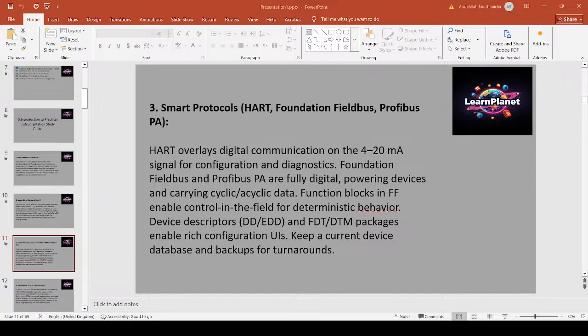Use the digital diagnostics to trend device health, zero drift, and valve trouble, and set predictive maintenance work orders. Example: use HART diagnostics to spot a transmitter with increased noise before it fails, and schedule replacement during planned turnarounds.